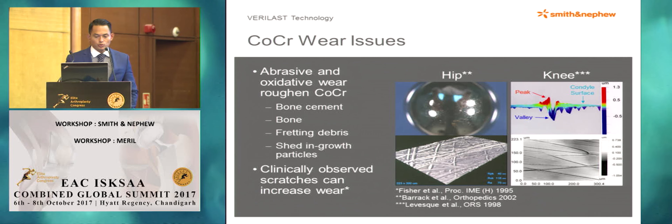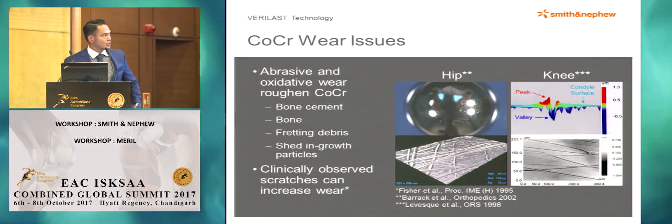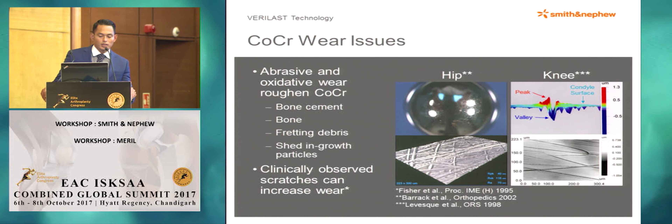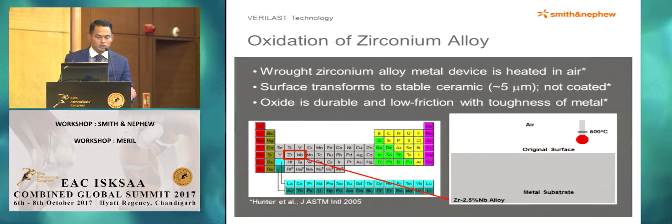We saw some wear issues with cobalt chromium. Abrasive and oxidative wear does roughen cobalt chromium, as shown here in these slides. Whether it's bone cement, bone, fretting debris, or shed in-growth particles, it was clinically observed that scratches can increase the wear. So we wanted to avoid and potentially address some of these pitfalls.